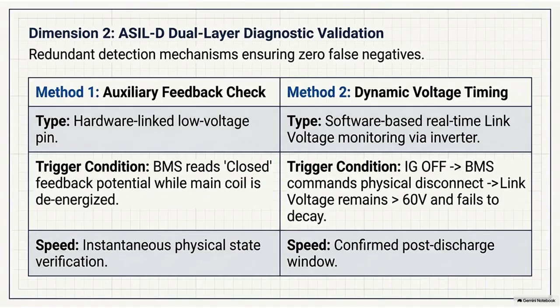If the software watches that link voltage decay curve, and the voltage stubbornly stays above a critical safety threshold, typically defined in safety standards as anything above 60 volts, for longer than the calculated discharge time window, the system has its irrefutable independent proof. The circuit is still live? The circuit is still being fed power. The main contactor is fundamentally welded.